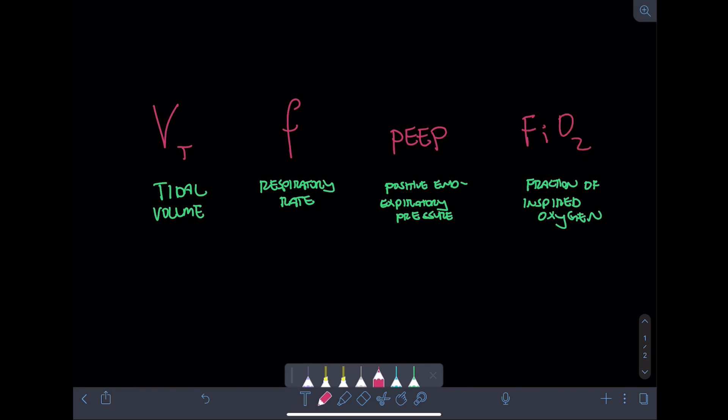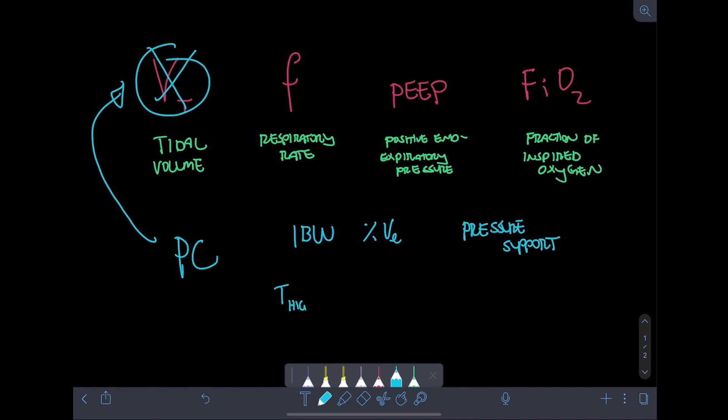Now there are many different types of modes, some of which come with settings different than what you see here. For example, pressure control substitutes a pressure for a volume, or smart modes might have ideal body weight or a percent minute ventilation. Spontaneous breaths may have pressure support, or bi-level may have a time high and a time low. These will be covered in another video, but for the most part, there's a high chance that your intubated, sedated patient will be on some form of volume control, which have these four settings here.